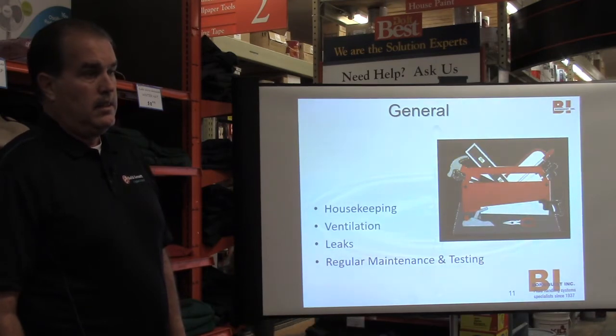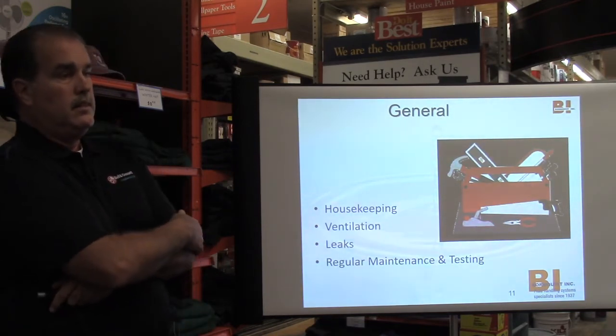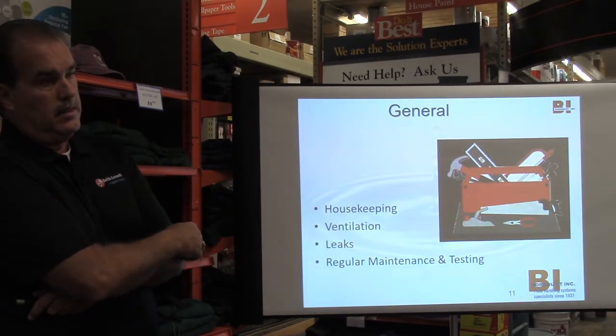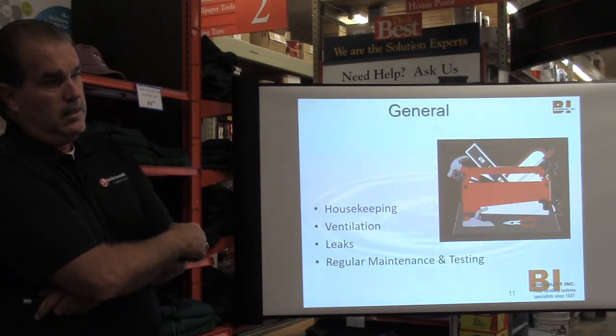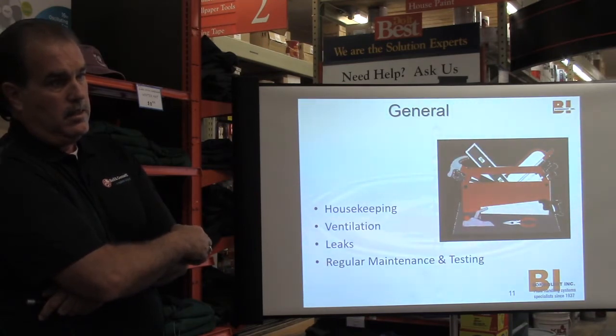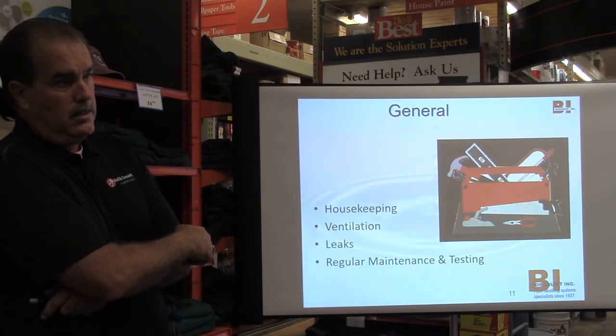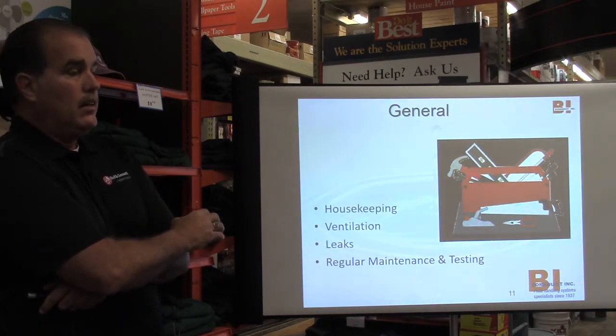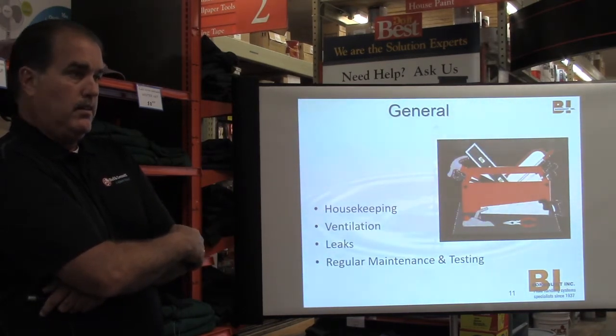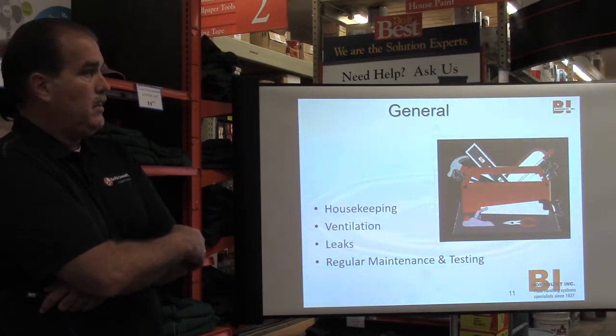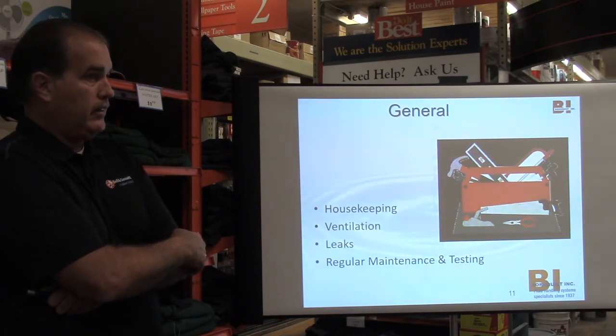Hot water heat, there's no water treatment. Recent maintenance guy said, this is my mother's building, another building, said that there was some repair he needed to do, so he drained the water. He said, but I really don't want to do this normally, except we have to here. Was he right there that, except for fixing a pipe, you shouldn't change the water, meaning drain and replace the water? Unless the water is filthy and dirty looking and stuff like that, you really don't need this. You don't need to flush hot water systems on a regular basis.